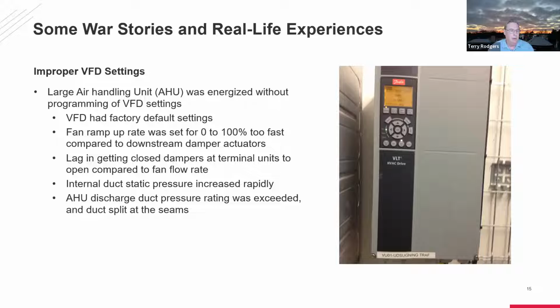An example here of a poor setup is VFDs. They're everywhere. They control fan speeds, pumps, et cetera. In one example, we had the fan ramp rate faster than the ability of the VAV boxes downstream to open up. So when they started the system, it ramped the fans up faster than they could relieve through the VAV boxes, and it overpressurized the ductwork and basically blew the ducts up.